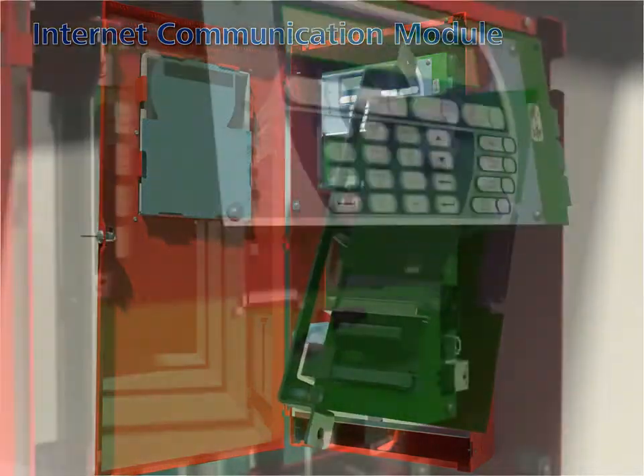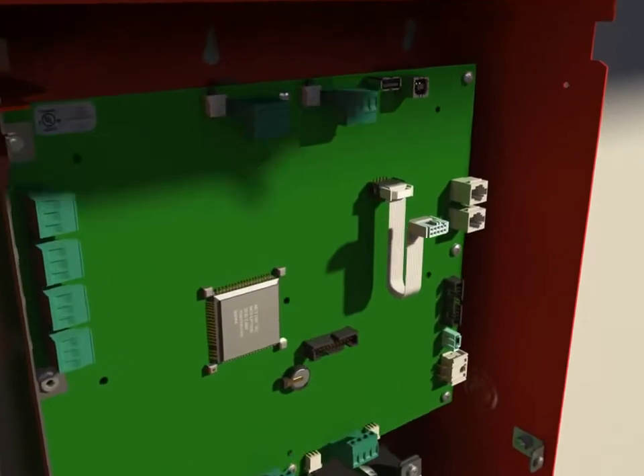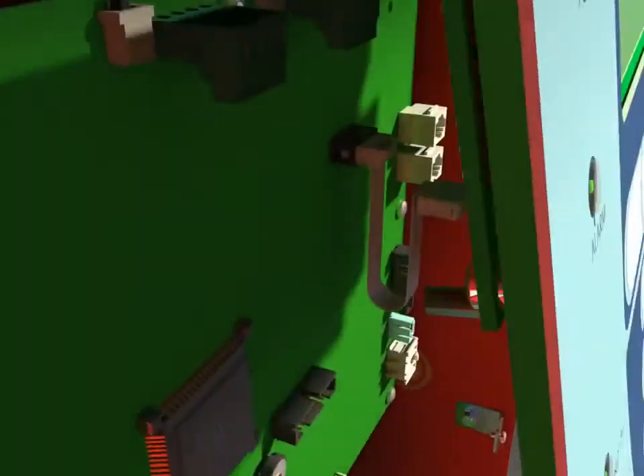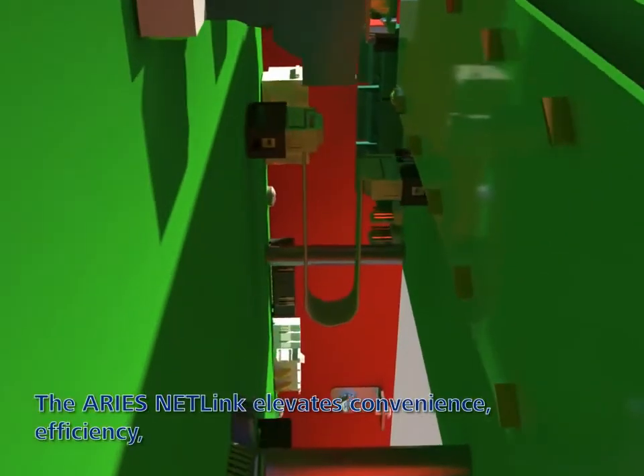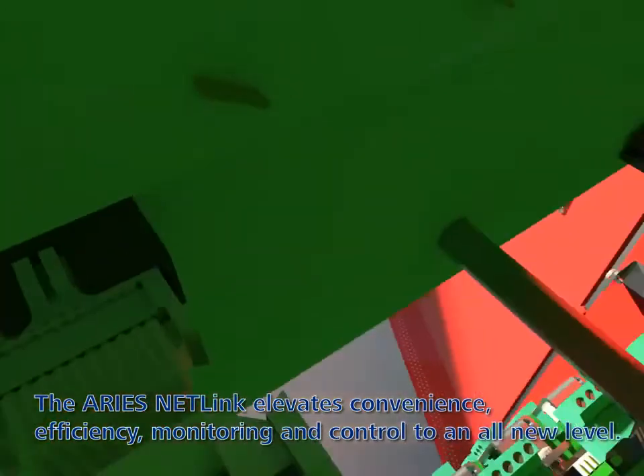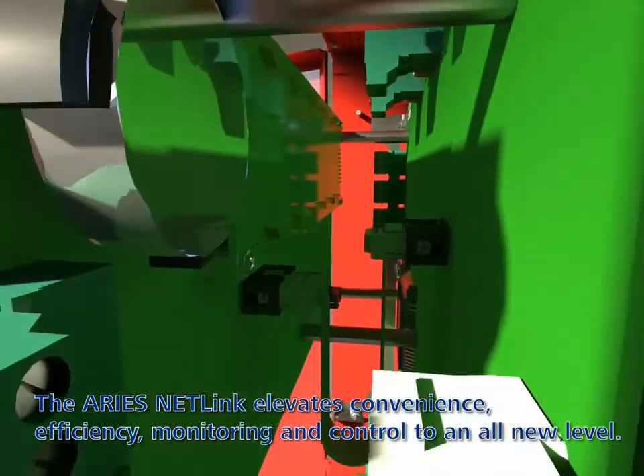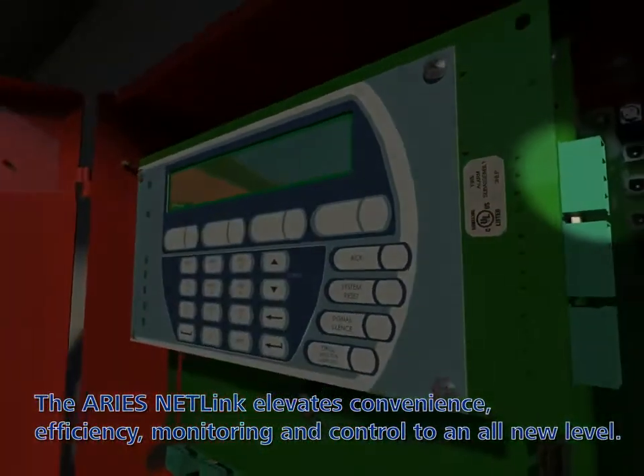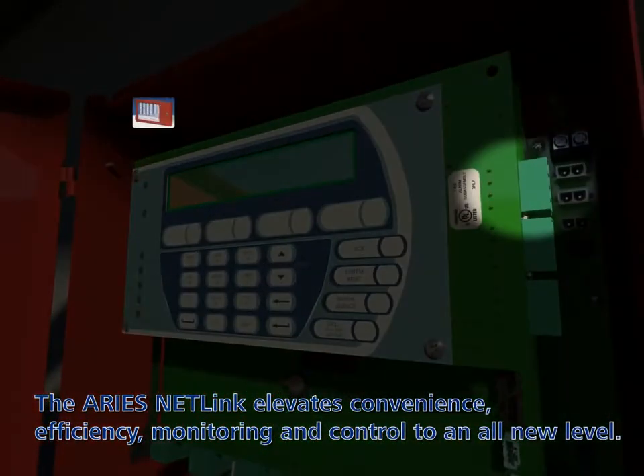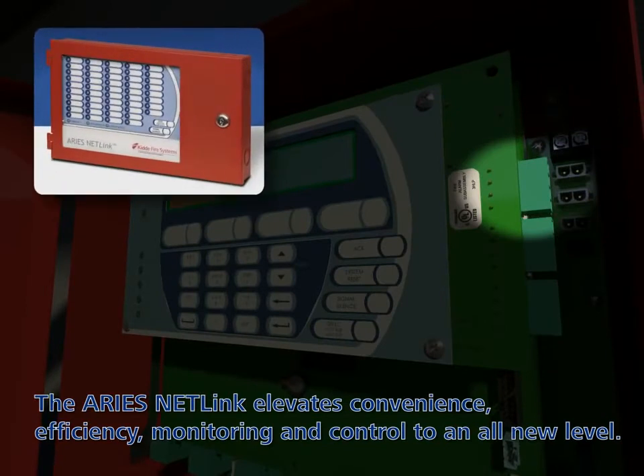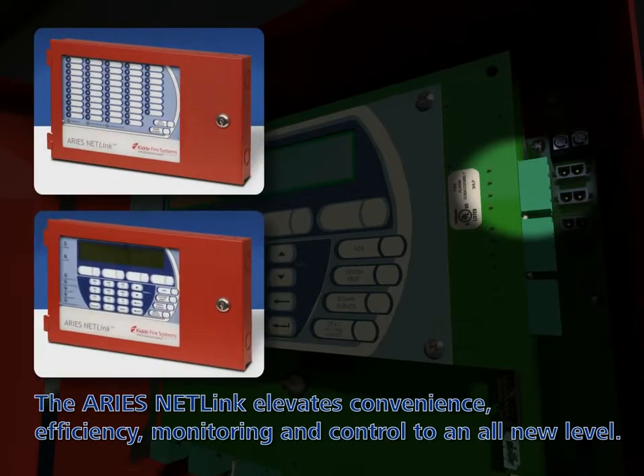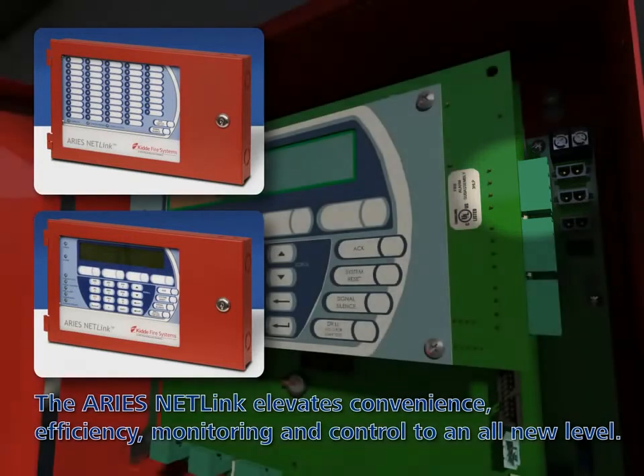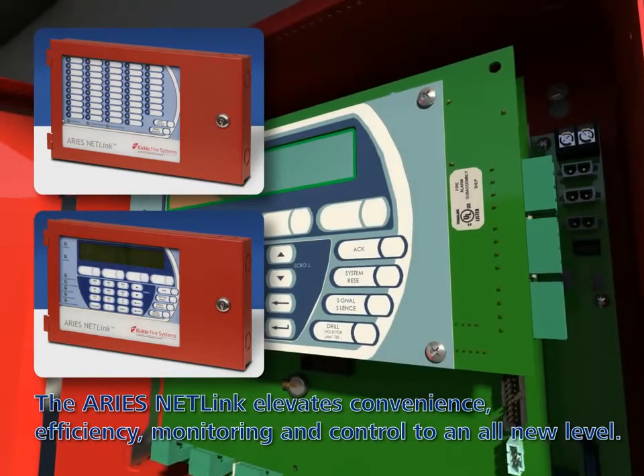The control unit is also equipped with an RS-485 remote annunciator bus that supports up to 31 annunciator modules. These include up to 16 remote LED annunciators, 15 remote display control modules (RDCM), and 16 ATMR and ATML drivers.